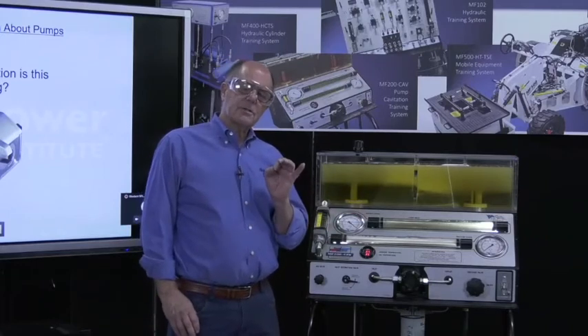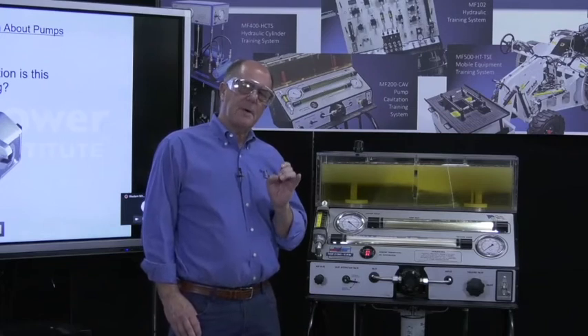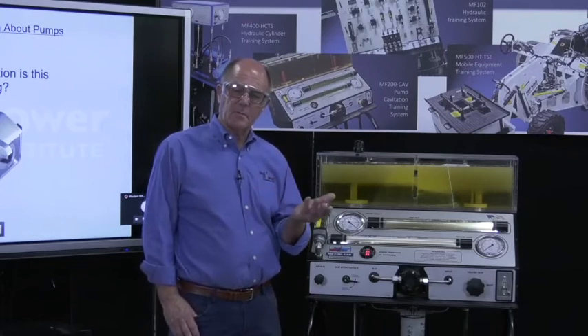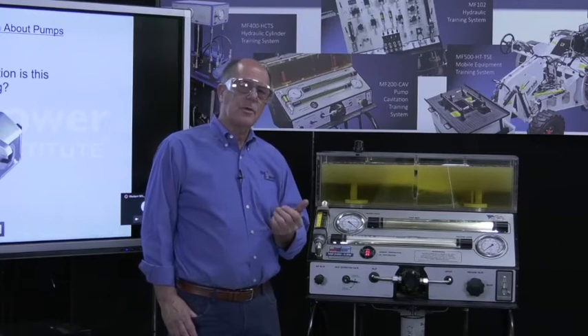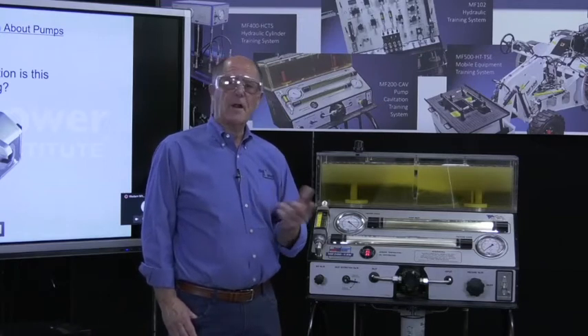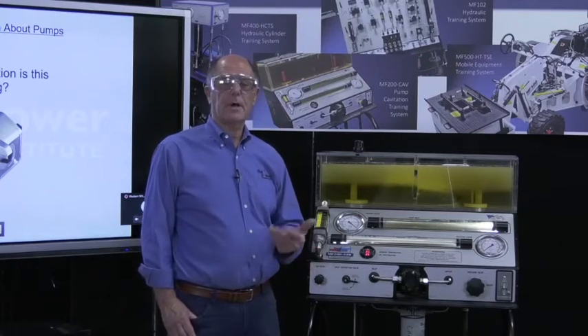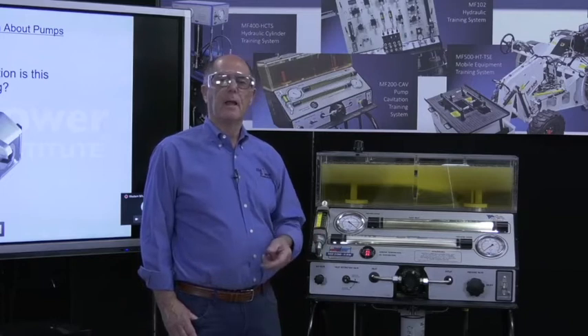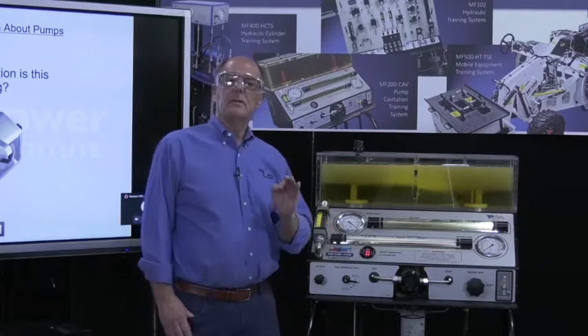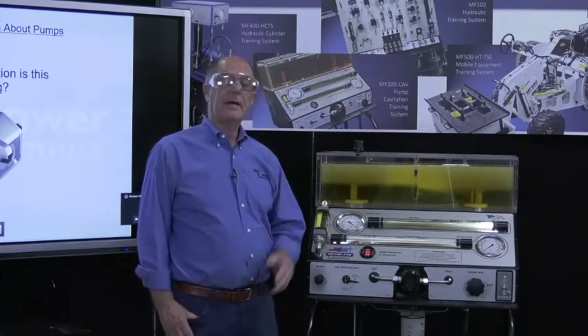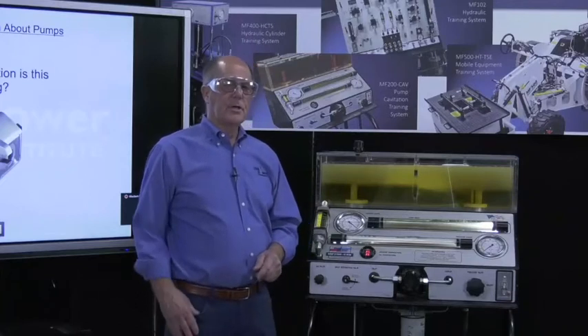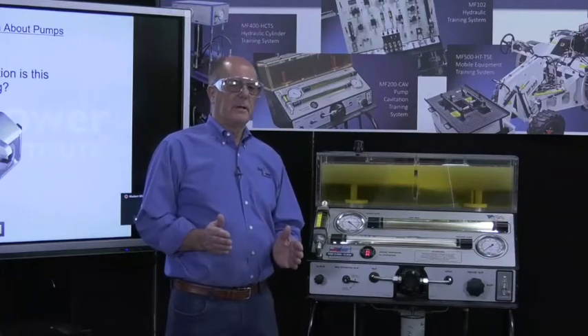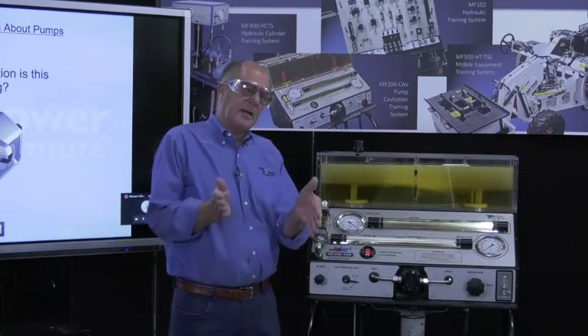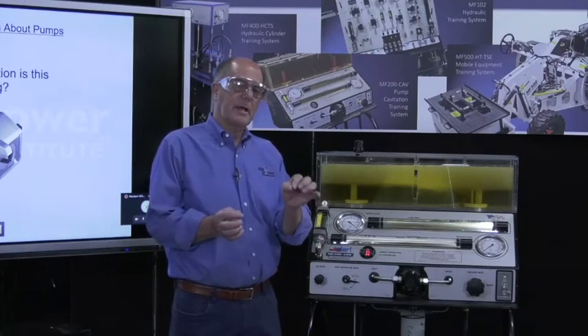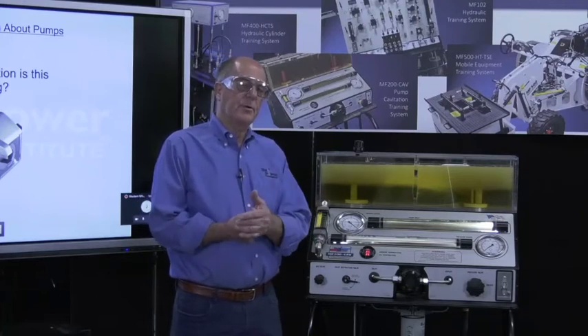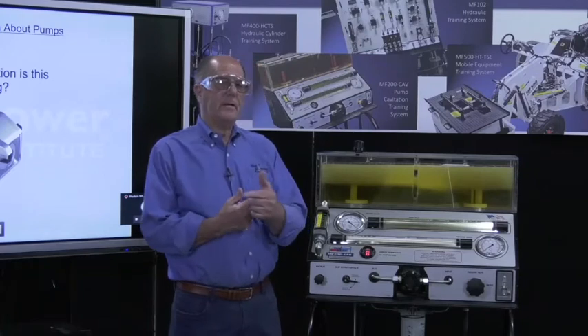I often ask students, have you ever tested a hydraulic pump before? And some will say yes. And I'll say, what did you use? And they'll say, I used a flow meter. What else? Pressure gauge. What else? Nothing. Cavitation drops the flow. Cavitation drops the pressure. So in other words, isn't that an incomplete test if I don't check inlet restriction? All of those elements that deliver oil to the pump could affect flow.